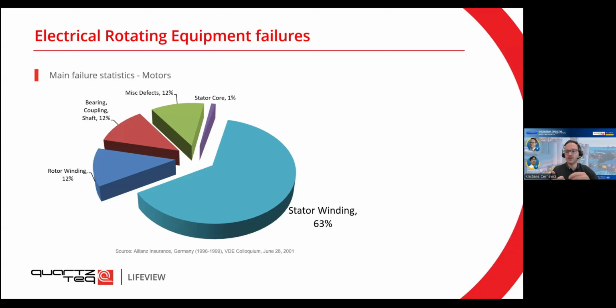So first of all, we need to monitor how the stator winding is doing. We need to monitor how the rotor winding is doing. And then we need to monitor what is happening with the bearings, with the coupling, and the shaft. So if we cover all these three parameters, if we monitor them, we can be fairly certain about the health of the machine. And this also gives us essentially the idea of what kind of measurements we need to do.